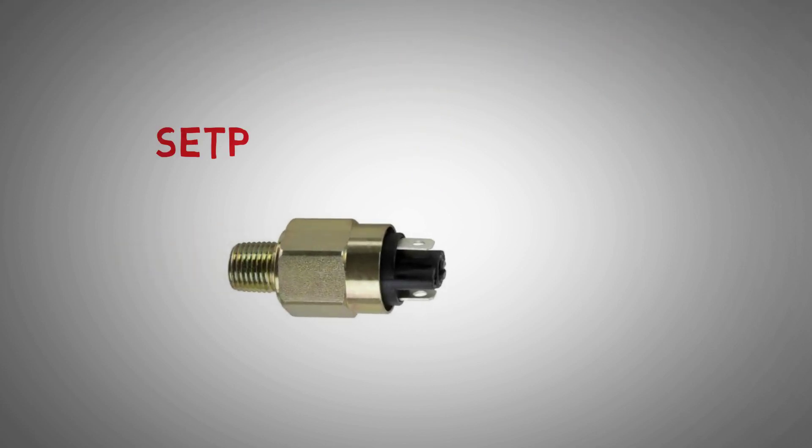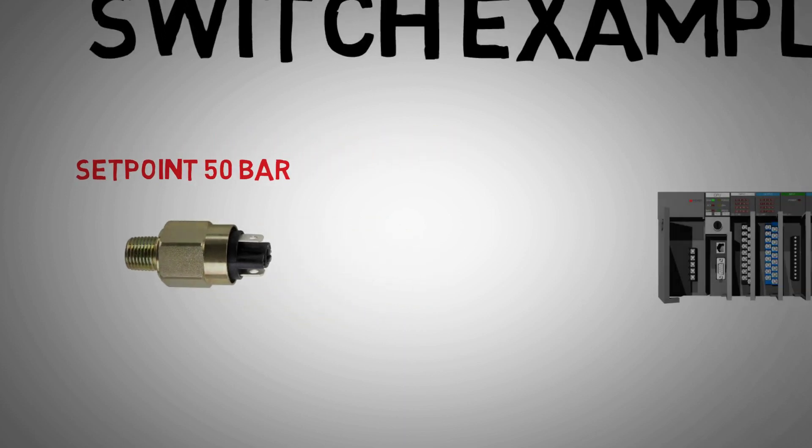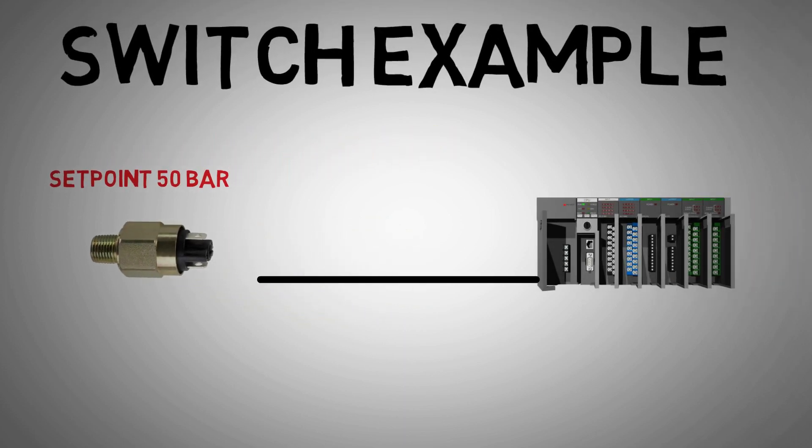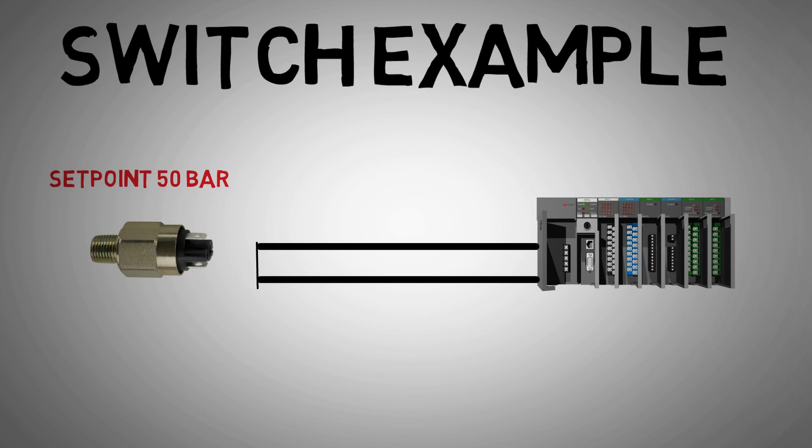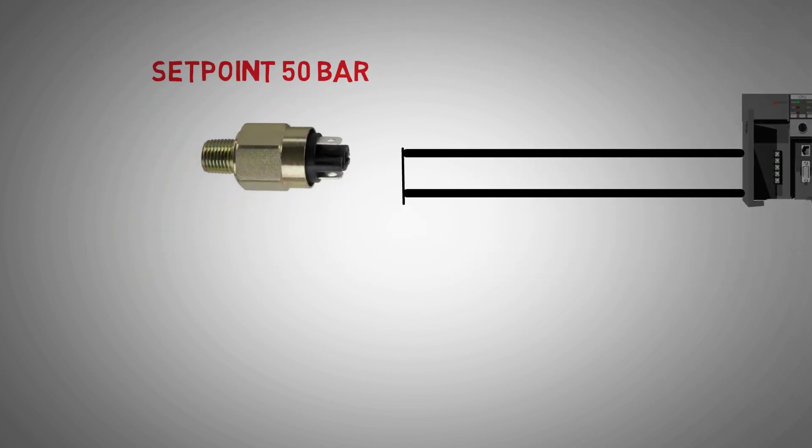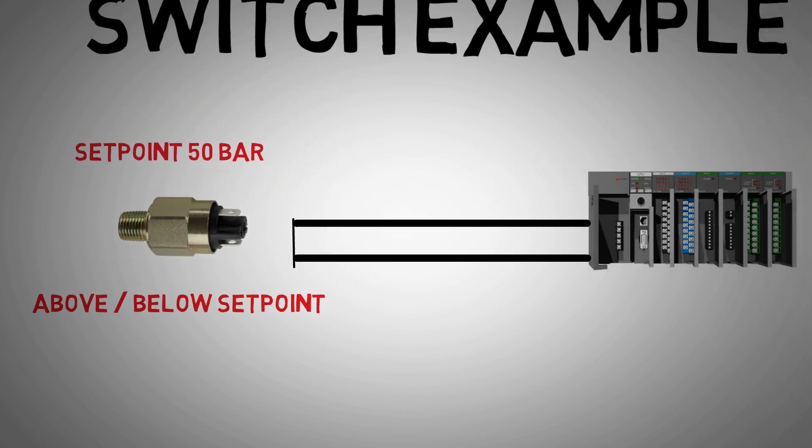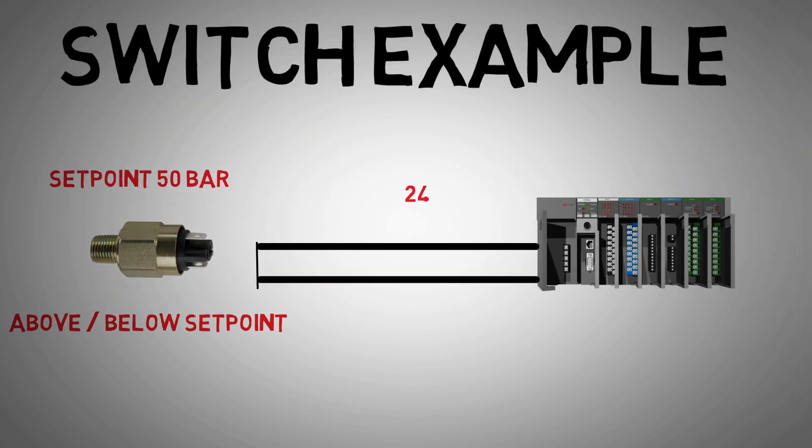Let's look at an electronic pressure switch. The switch will have a set point, let's say 50 bar. The switch will open or close an electrical contact depending on if the pressure is above or below this value. The electrical contact within the switch will be changing the signal, usually 24 volts DC, back to the control system.